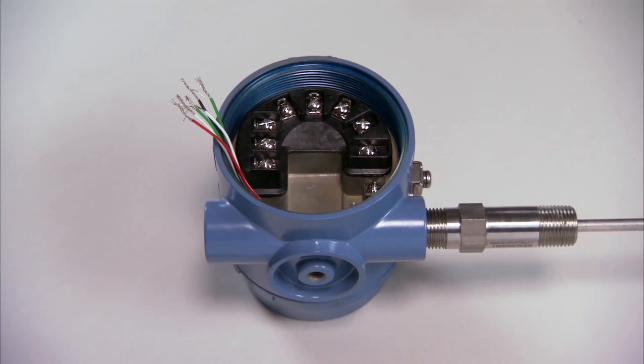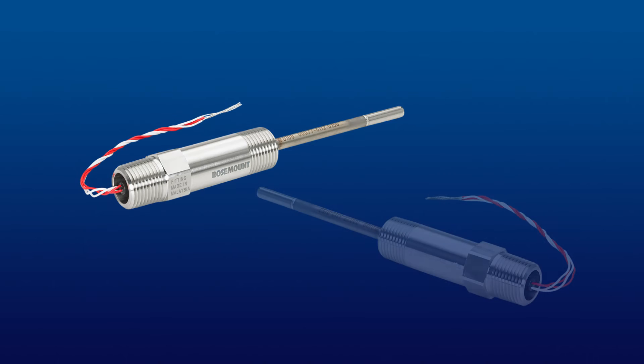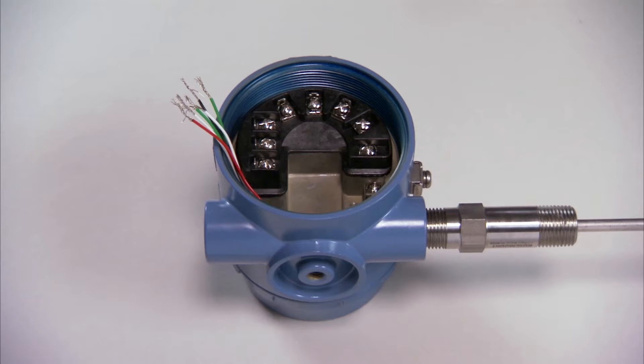The sensor wires and power connections must now be attached. Because the 3144P can accept two separate sensor signals, the transmitter can be wired using a dual-element sensor or two individual sensors. Remember, the wire colors will vary based on manufacturer and sensor type.